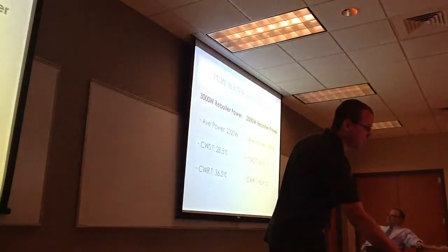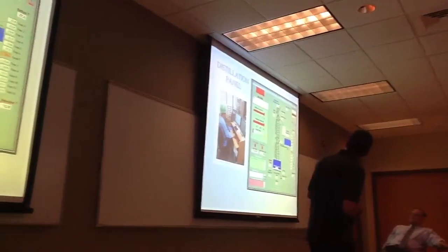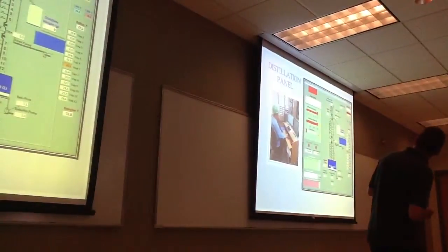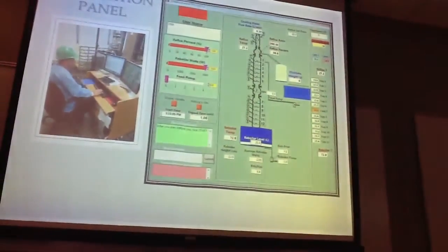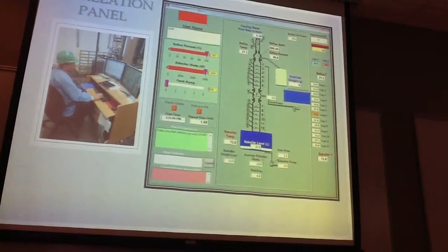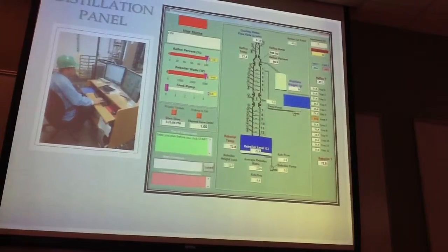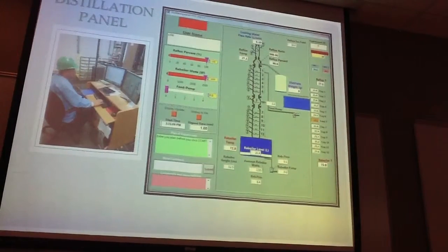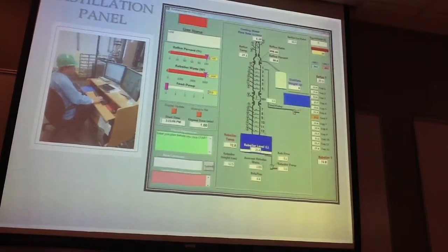And actually, when I was talking about the cooling water, I forgot to mention that at the very top of the actual distillation column, there is a flow rate that reads 5.1 liters per minute. Originally, the reason we were running it was the idea that I would do a heat balance, an energy balance, using that and the cooling water temperatures, but then I've been informed that that is a meaningless measurement or not an accurate measurement, so we have to figure out what our flow rate actually is. And that is part of the cooling water issue.